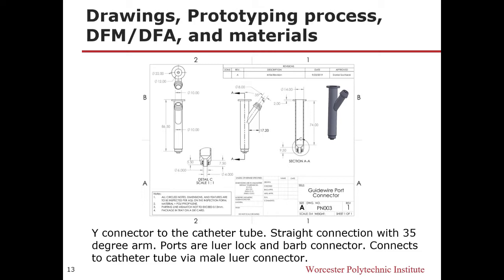Our design also includes a Y-shaped port connector, which is to connect the catheter with the pressure meter and the syringe. It has a 35-degree arm. The manufacturing of the port can be carried out either by Stone Medical Devices or Merit Medical. The material can be either a combination of ABS and PP for the first manufacturer, or polycarbonate and PVC for the second. The DFM process includes injection molding, and the DFA process includes single injection molding and screwing the catheter tube onto the port connector. In the testing and evaluation process of the port, first of all, we want to test the mechanical properties. We also want to test the connection between the port and the catheter.